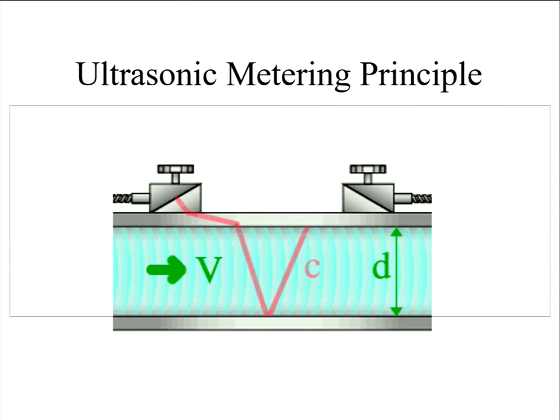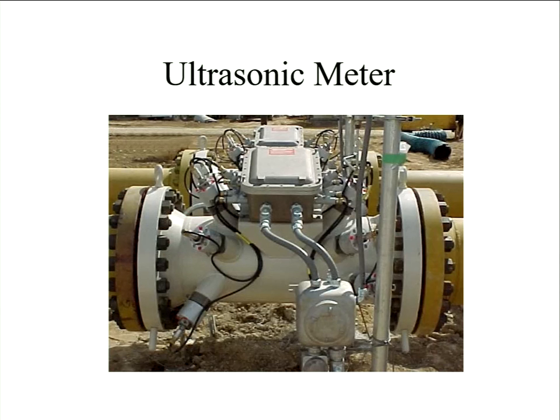I've not said an awful lot about other measurements. So we've got temperature, calorific value can be very important, and often you'll have more than one chromatograph. Again, there's different ways of doing it. You can do a full gas density and an equation and infer the properties, or for quick measurements, there are other ways of doing it. Gas quality, so Wobbe, effectively the way that the gas burns, the relationship between calorific value and density, dew points, sulfurs and hydrogen sulfides and density, and so on and so forth.